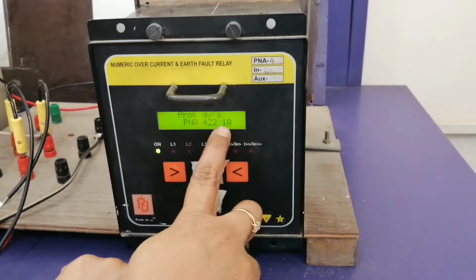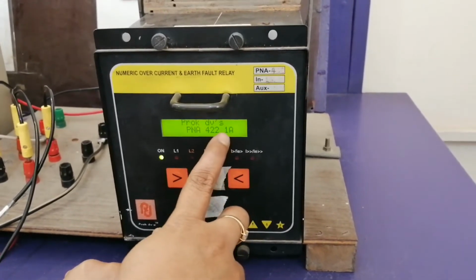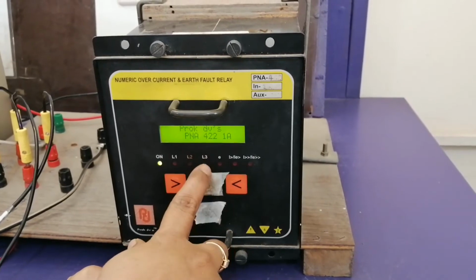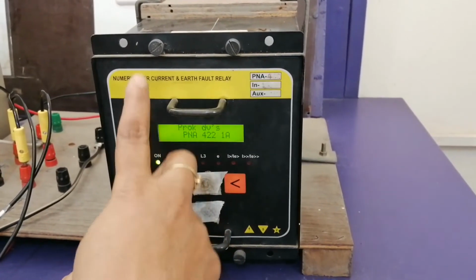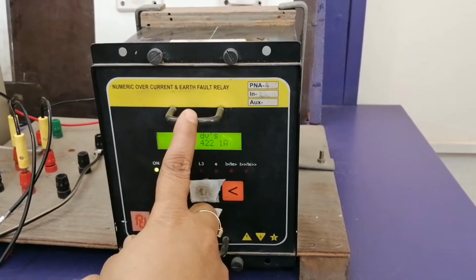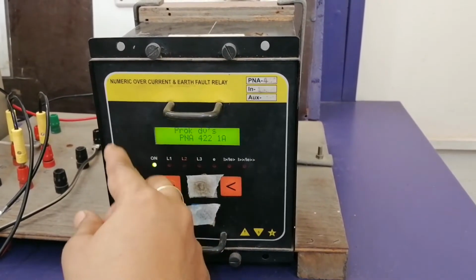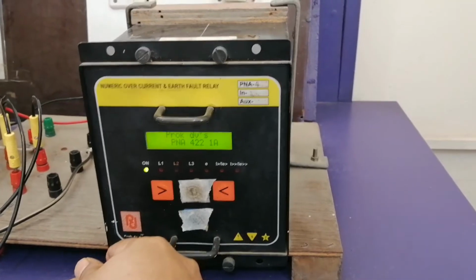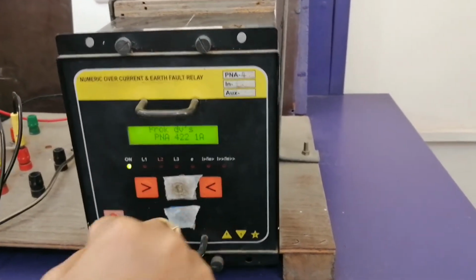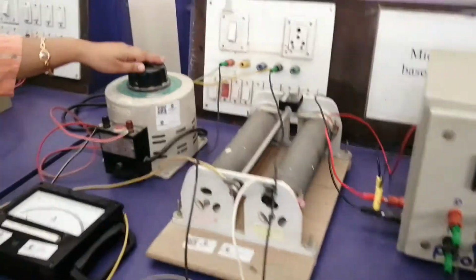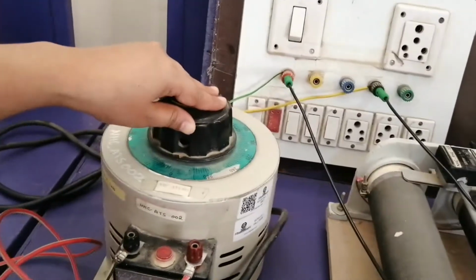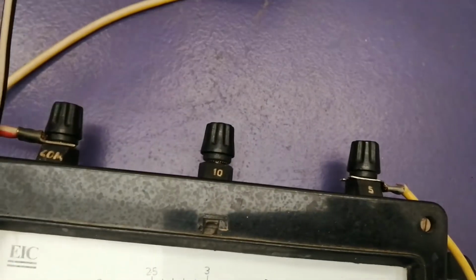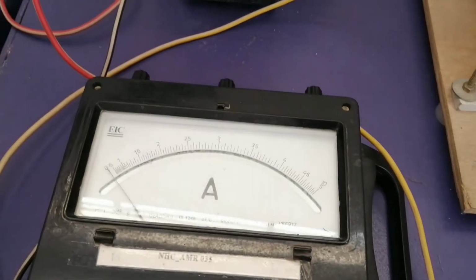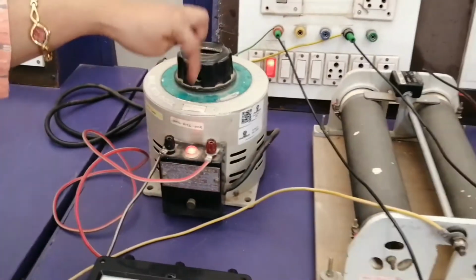Now I have set my PSM to 1.5 and my rated current is 1. So 1.5 into 1 is 1.5 ampere. My relay will sense it as a fault if the fault current is more than 1.5 amperes. Now how to create a fault here? Fault is created by an auto transformer. I am creating a fault of 3 ampere in this ammeter by switching on the supply switch S2. You can see S2 has glowed.